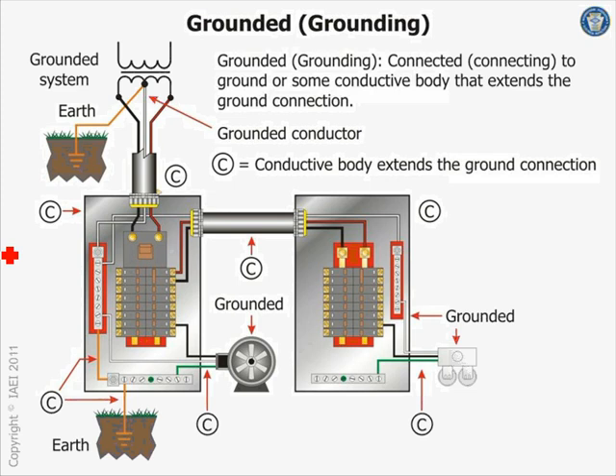You wouldn't do this on a system like this. That's a problem with the power system that we have here: if you lose a neutral and you're not bonded to the ground, you have an open neutral, you burn equipment. You burn buildings, literally.